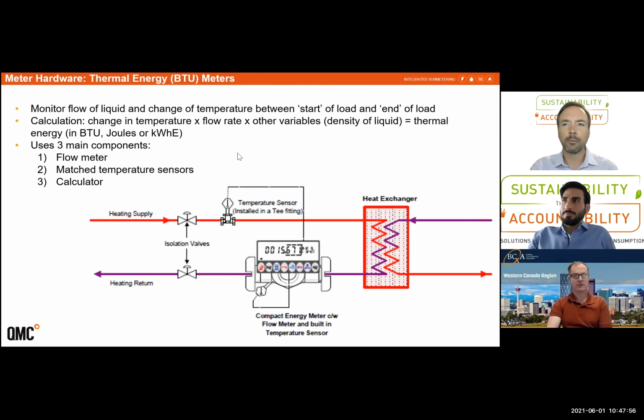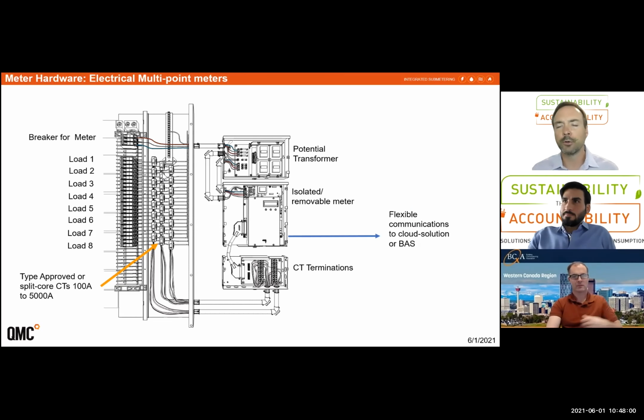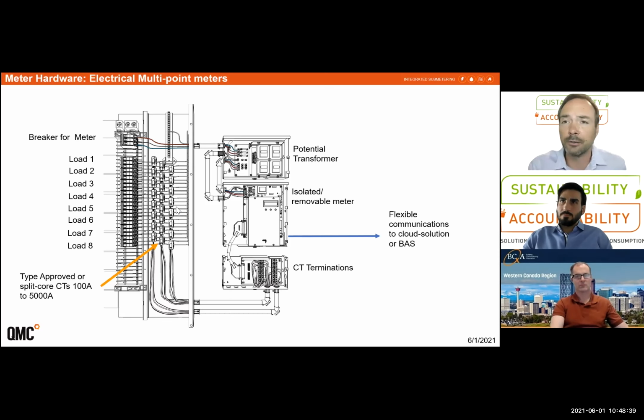Yeah, so in a typical commercial application, we would look at utilizing one of these multimeter systems for metering plug loads, where you would go into a distribution panel, and whether they're 15 amp, 30 amp, or 60 amp breakers that are feeding a variety of different plug loads within the office floor, as an example, you would use current transformers for that. And when I was mentioning you get a very low cost per meter point, it's when you're utilizing these multimeter technologies, because the cost of the CTs is very minimal, like $15, $20, and then you're utilizing 1 meter head essentially for up to 24 CTs. There are other manufacturers that do up to 40 CTs or even 100 CTs on some devices. You get a very low cost per meter point when you do that.